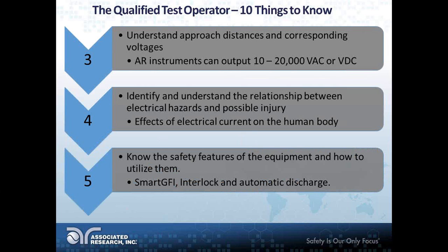Number 5, know the safety features of the equipment and know how to use them. Every piece of equipment will have some type of safety feature on it, hopefully if it's manufactured well. For example, our hipot testers have our patented smart GFI circuit, which is able to recognize if there is stray current flowing to ground. Because what the unit then assumes, if there's stray current flowing to ground and it's not coming back through the return, somebody must be touching the device under test, and I'm going to shut off immediately. And on some of our units, you can set the threshold. On some units, it's a default 400 microamps, and it'll shut off if it senses any stray current beyond that.